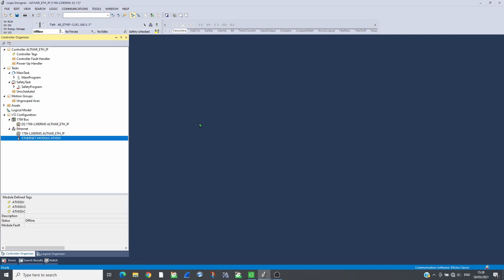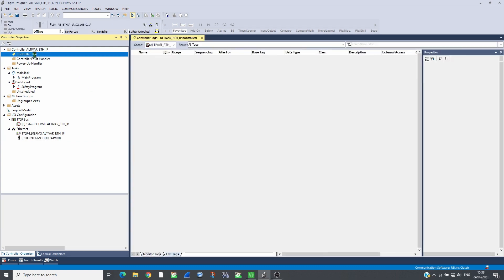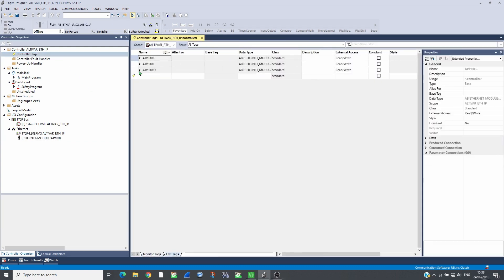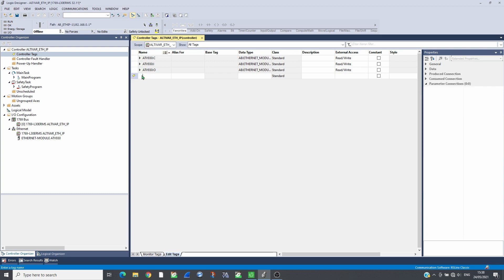Set the RPI to 10 milliseconds. Add tags to the drive inputs, ETA, RFRD, LCR, and outputs, command LFRD, to have them in one monitoring view.